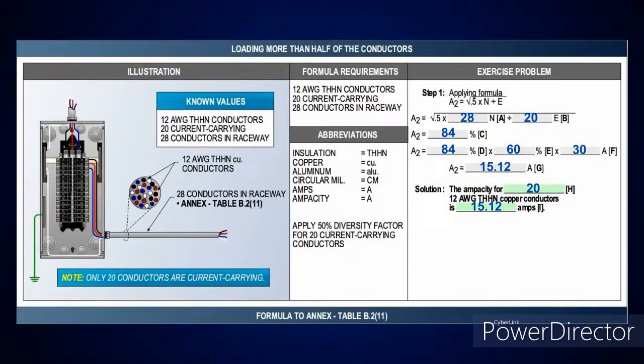Okay, now let's look at my diversity here. This is a different type of diversity, and you're counting. I have 28 conductors in the raceway, but 20 of them are current carrying. The last one I did, I had a 50% diversity because only 14 were current carrying. So you'll use this formula right here to get your percentage, but you're still going to put the 60% on it like we did for the 28 conductors. You'll have this calculation at 0.5, which is a constant. Then you've got the square root of the total number of conductors, 28, and E is the number that are current carrying. I'm going to divide that into that 28, and that's 20 conductors. That's going to give me 84%. So all I'm going to do is the same calculation that I just did for the 50% diversity. The only thing I'm doing different is adding 84% to it.